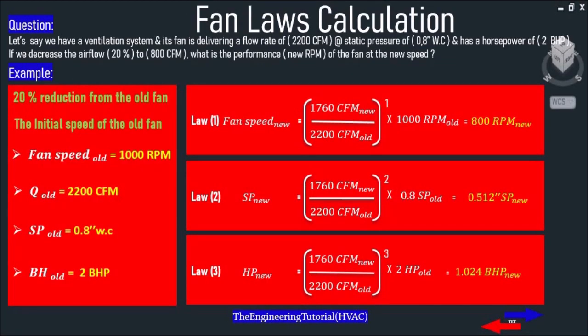In order to figure out the performance of the new required fan after a reduction of airflow at the new speed, we'll use an example. Let's say we have a ventilation system delivering a flow rate of 2200 CFM at a static pressure of 0.8 inches of water column and a brake horsepower of 2. If we decrease the airflow by 20 percent to 1760 CFM, what is the new fan performance and new RPM?